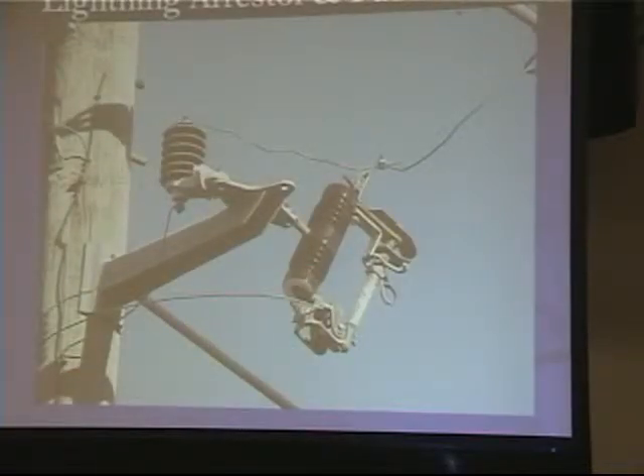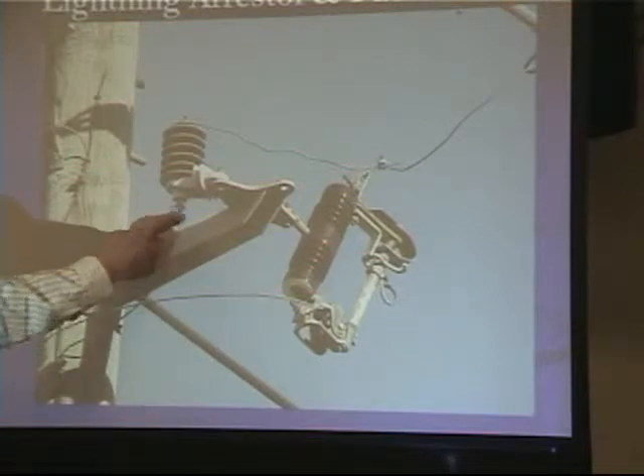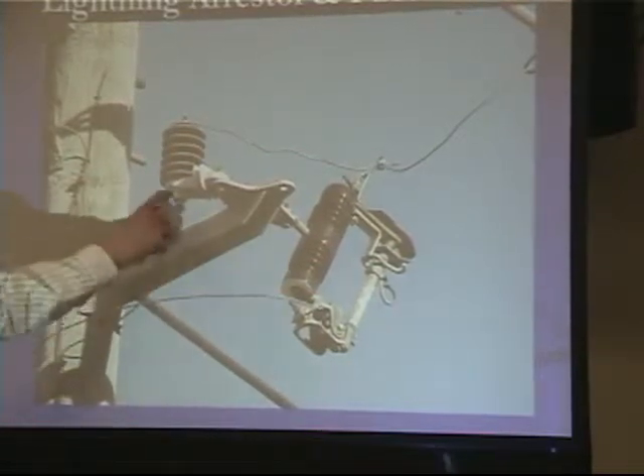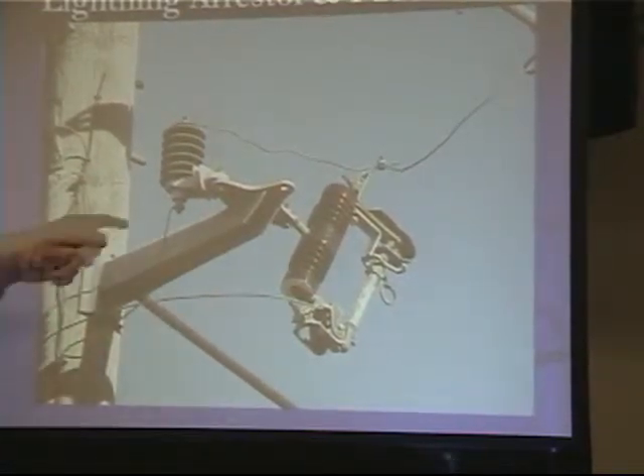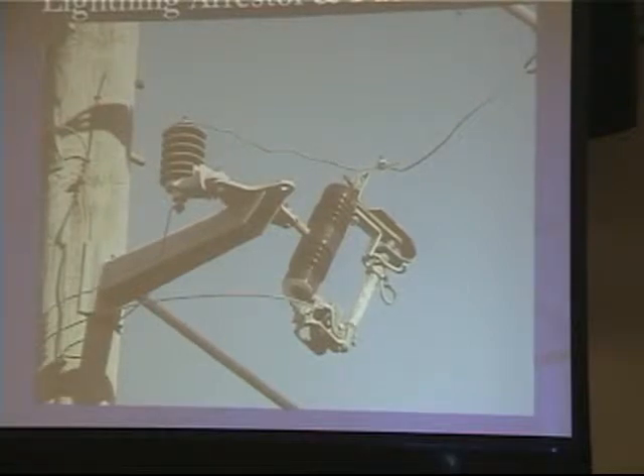Lightning arresters, I mentioned those can fail. This particular one is an interesting example because they've installed the cable at the bottom wrong. He's got a sharp edge on the connection right at the bottom of it, which is right here. It should be bent this way, not this way. If you bend it this way, it would act like a better lightning arrester. In that position, it's probably not a real good lightning arrester, but it's just going to make noise. Is it too close to the support below?